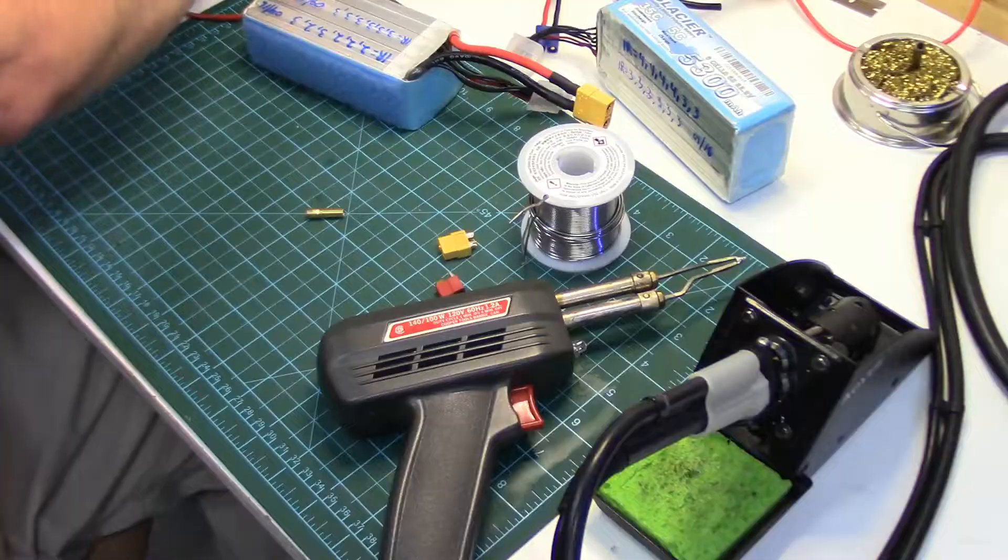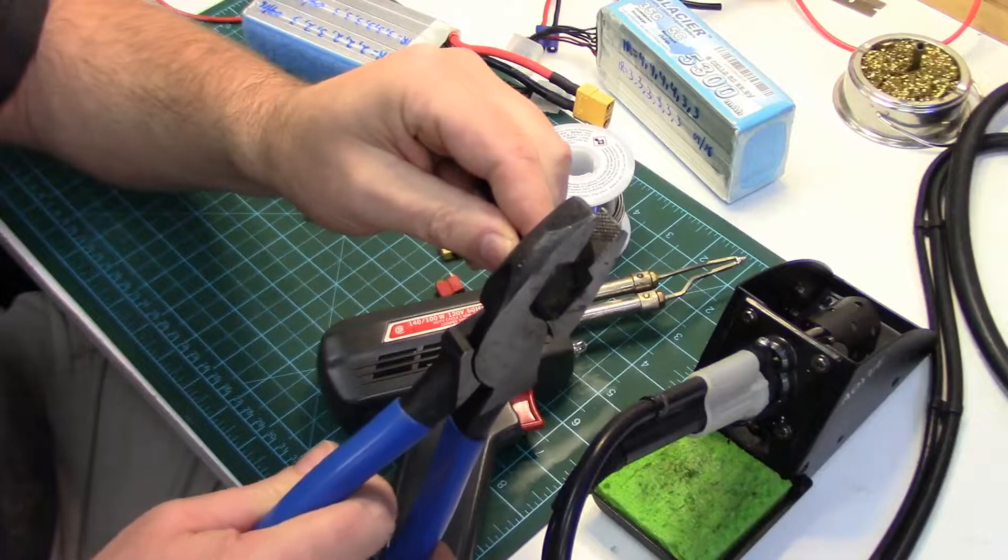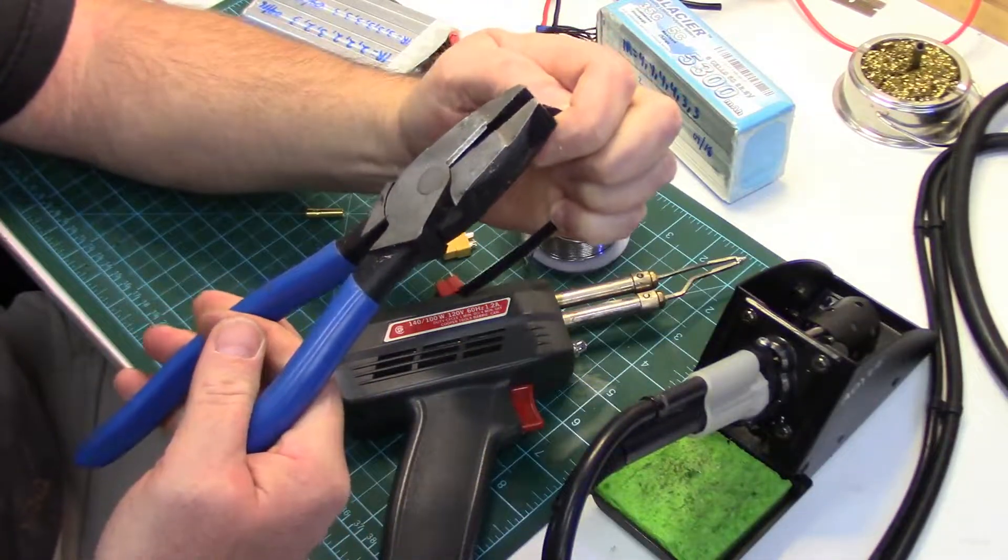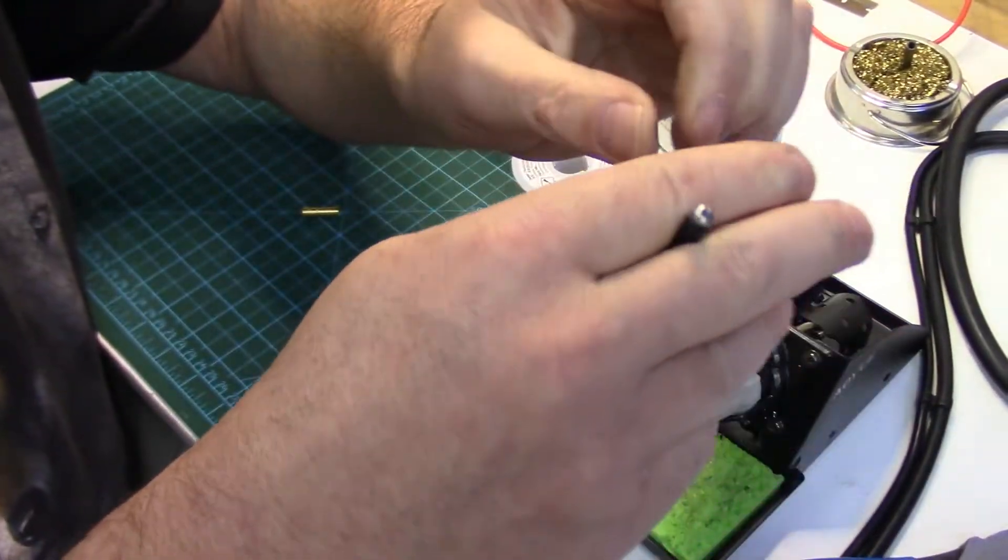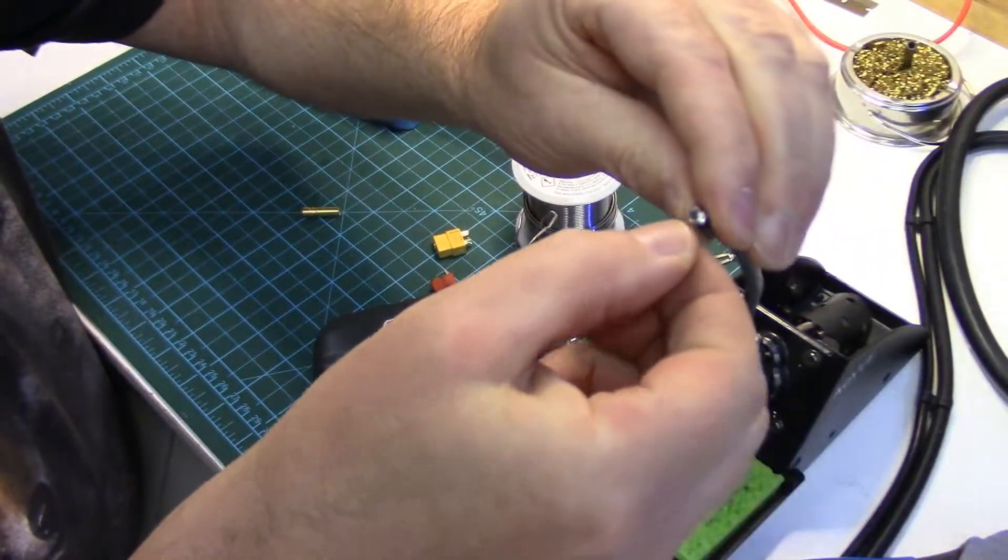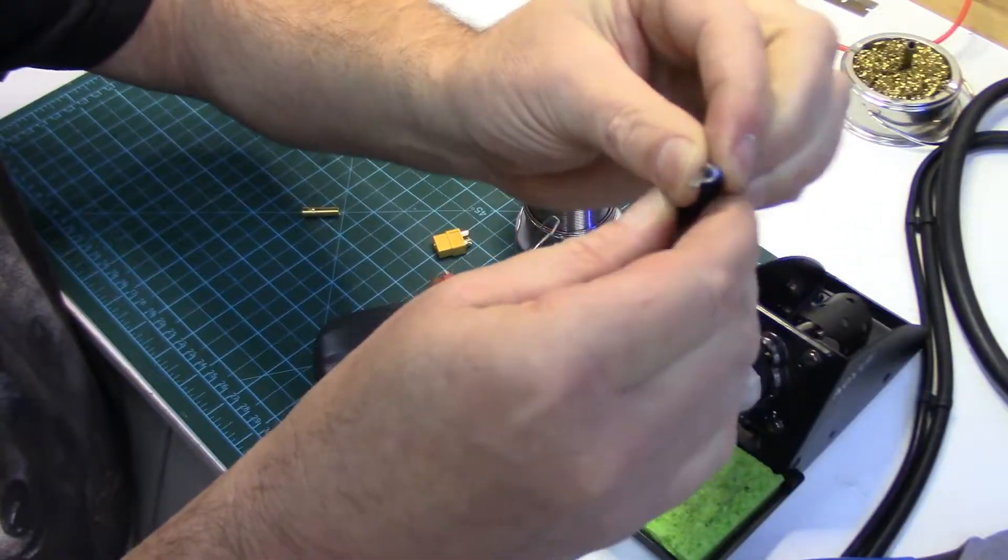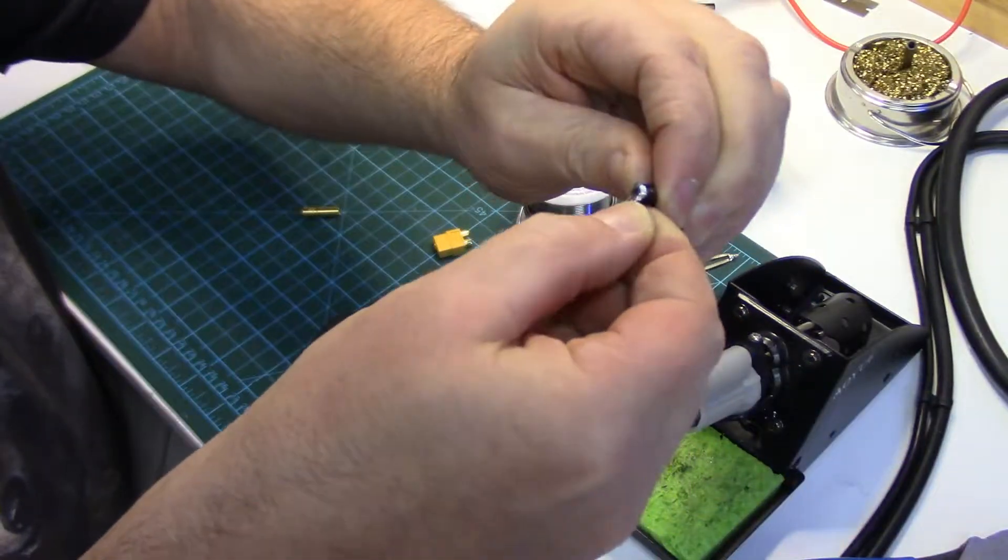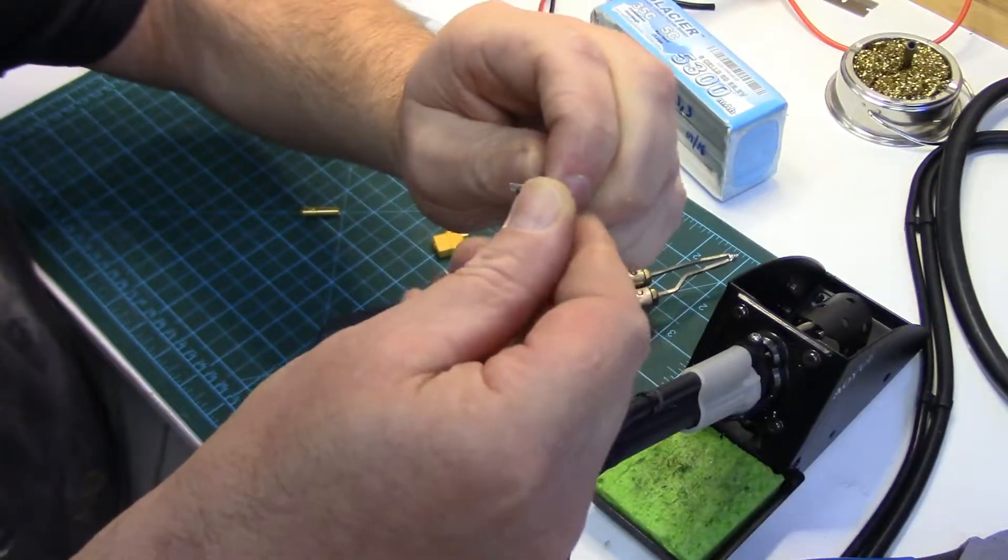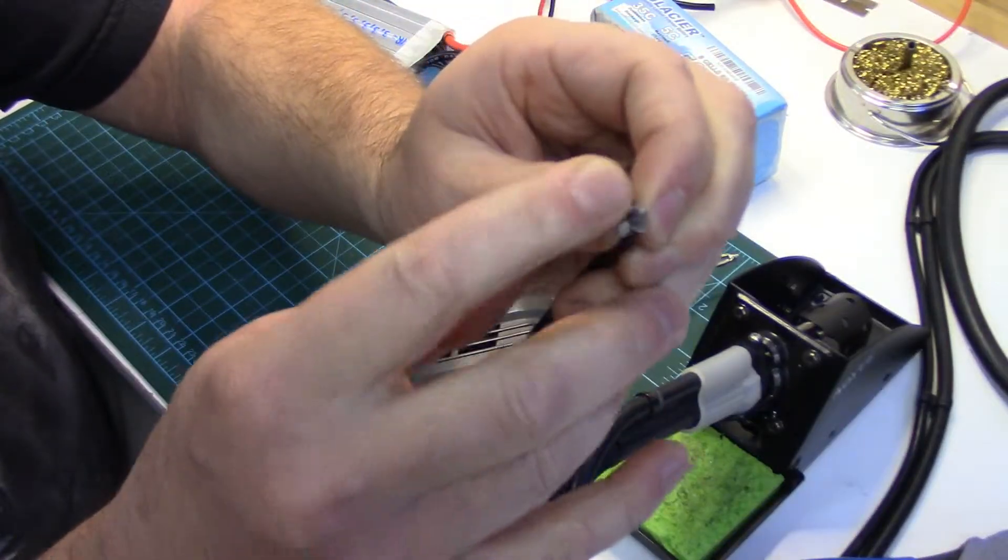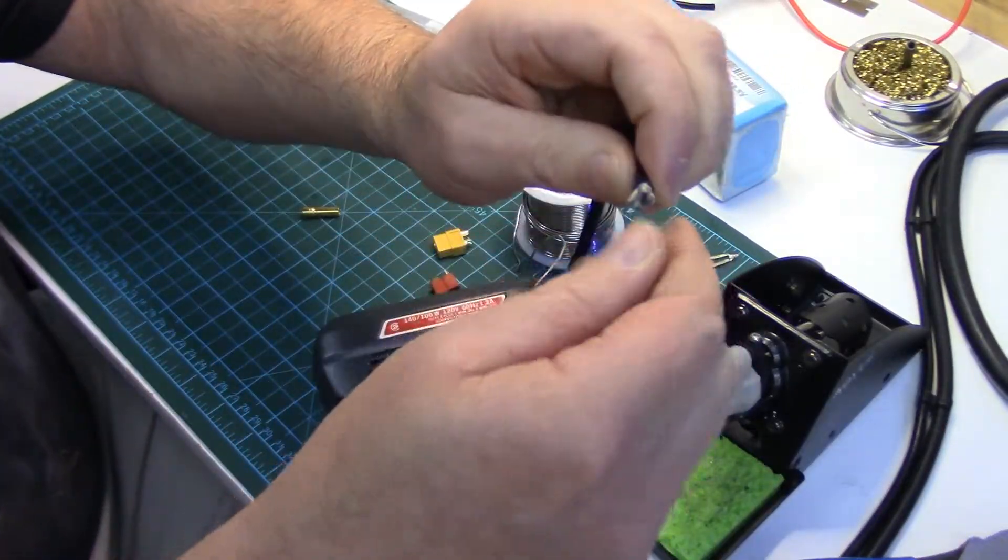There's solder all the way around it. However, let me just get my clippers out. I'm just going to cut the end of it off. I don't know if you can see this. Hopefully this will show up. But yes, the outside of the wires are well tinned, but none of the inside ones are. The inside stuff is all still just loose. So we didn't have good penetration there. The solder didn't penetrate all the way into the wire.